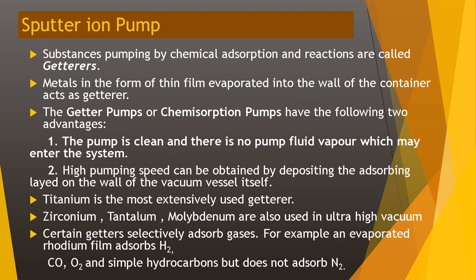Substances pumped by chemical adsorption and reactions are called getters. Metals in the form of thin films evaporated onto the wall of the container act as getters. Getter pumps or chemisorption pumps have two advantages: the pump is clean with no pump fluid vapor entering the system, and high pumping speed can be obtained by depositing the absorbing layer on the wall of the vacuum vessel itself. Titanium is the most extensively used getter material; zirconium, tantalum, and molybdenum are also used. In ultra-high vacuum, certain getters selectively adsorb gases — for example, an evaporated rhodium film absorbs H₂, carbon monoxide, oxygen, and simple hydrocarbons but does not absorb nitrogen.